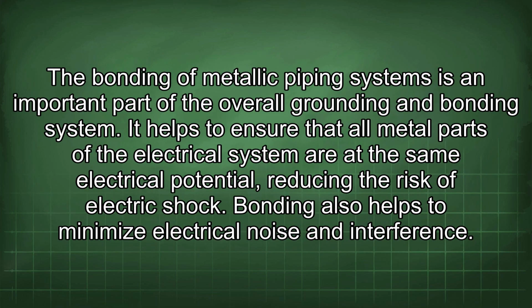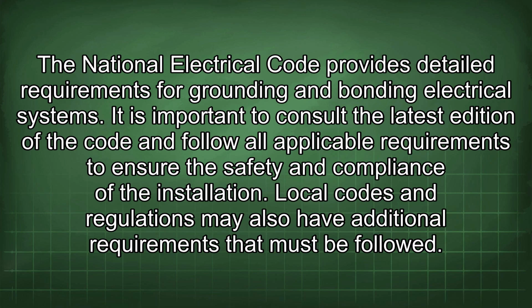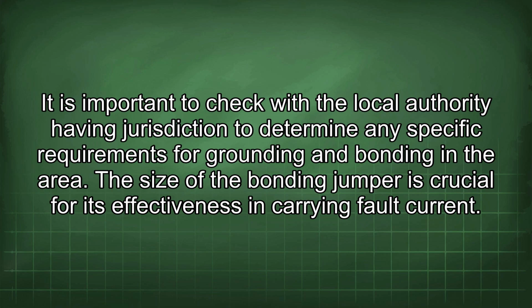The bonding of metallic piping systems is an important part of the overall grounding and bonding system. It helps to ensure that all metal parts of the electrical system are at the same electrical potential, reducing the risk of electric shock. Bonding also helps to minimize electrical noise and interference. The National Electrical Code provides detailed requirements for grounding and bonding electrical systems. It is important to consult the latest edition of the code and follow all applicable requirements to ensure the safety and compliance of the installation. Local codes and regulations may also have additional requirements that must be followed. It is important to check with the local authority having jurisdiction to determine any specific requirements for grounding and bonding in the area.